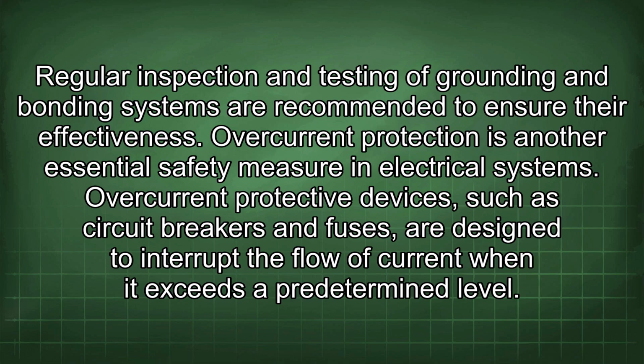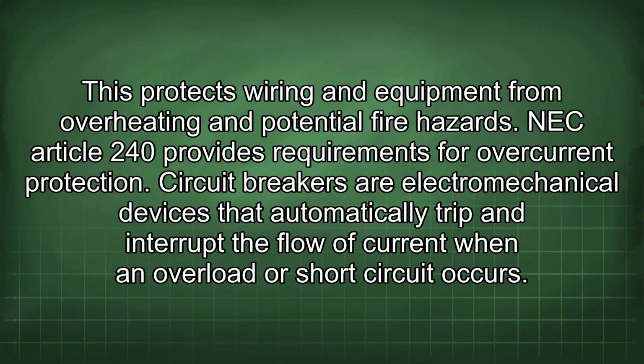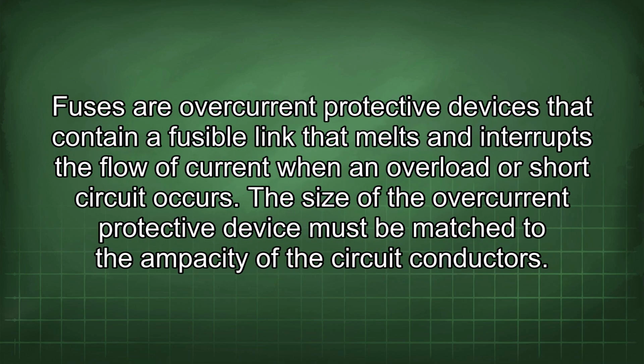Overcurrent protection is another essential safety measure in electrical systems. Overcurrent protective devices, such as circuit breakers and fuses, are designed to interrupt the flow of current when it exceeds a predetermined level. This protects wiring and equipment from overheating and potential fire hazards. NEC Article 240 provides requirements for overcurrent protection. Circuit breakers are electromechanical devices that automatically trip and interrupt the flow of current when an overload or short circuit occurs. Fuses are overcurrent protective devices that contain a fusible link that melts and interrupts the flow of current when an overload or short circuit occurs.